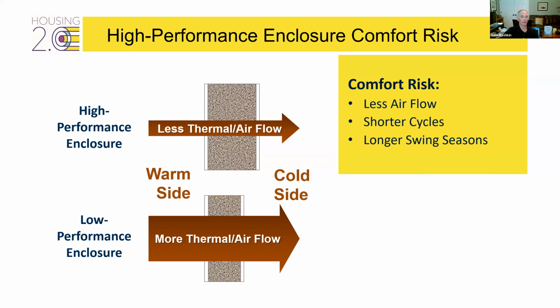We have shorter cycles because the buildings have so much reduced sensible cooling loads. The cycles are very much reduced, and when we have oversized equipment, which is the other poor track record we have in HVAC, we also have very short running times, so the coils don't get long enough to reduce humidity effectively. And lastly, we have longer swing seasons.